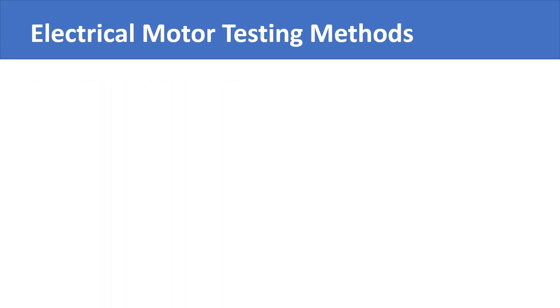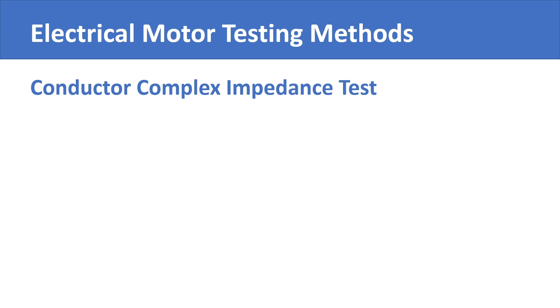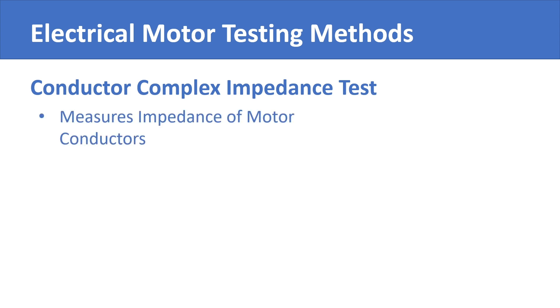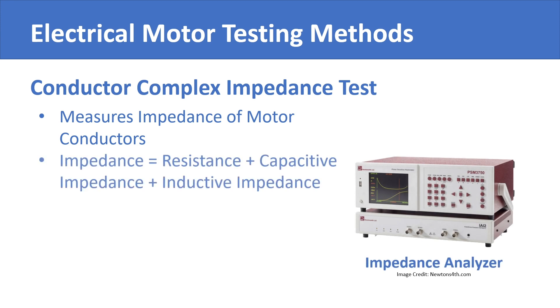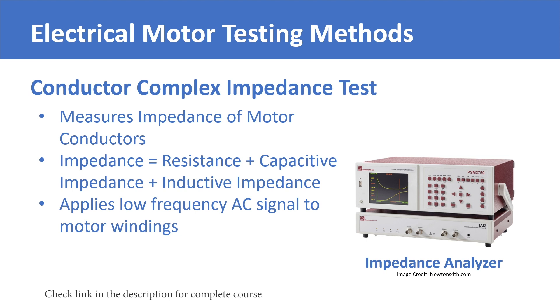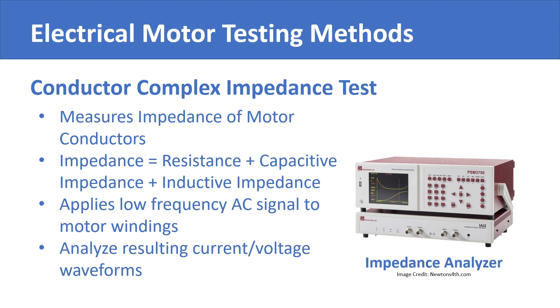Yet another test is the conductor complex impedance test. It measures the impedance of all the conductors in the motor by using a special tool called an impedance analyzer. Impedance is the sum of resistance, capacitive impedance, and inductive impedance. In this test, a low frequency alternating current signal is applied to the motor windings and the resulting current and voltage waveforms are analyzed. The results reveal any fault in the motor conductors, mainly windings.